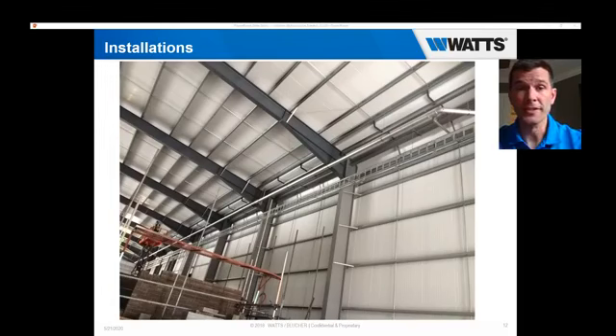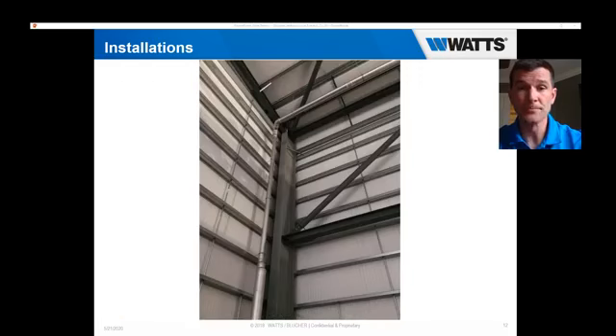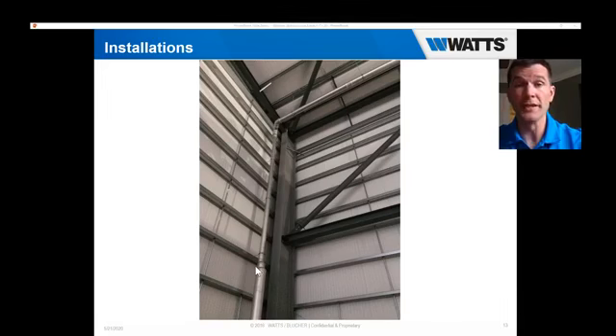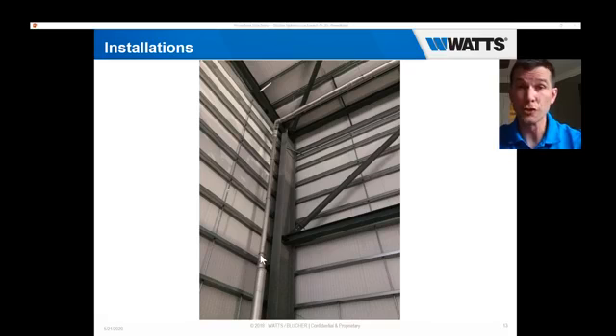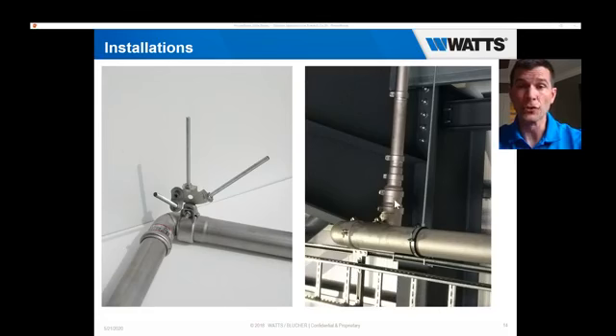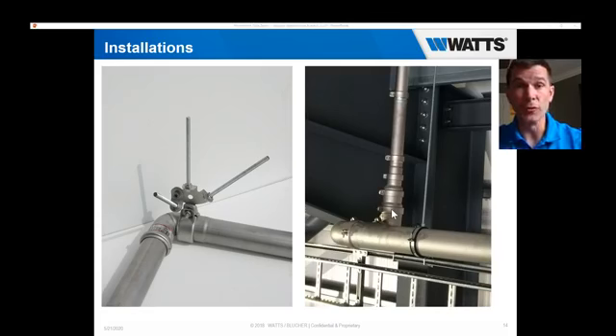Here are some pictures of siphonic systems we've installed. You can see the horizontal piping and the push-fit increasers used to transition from two-inch pipe to two-and-a-half, three, or four inch — being able to just push-fit the system completely together, similar to an erector set. Here's a closer-up picture of that increaser, as it goes through the piping to balance the pressure and flow rate of the system.